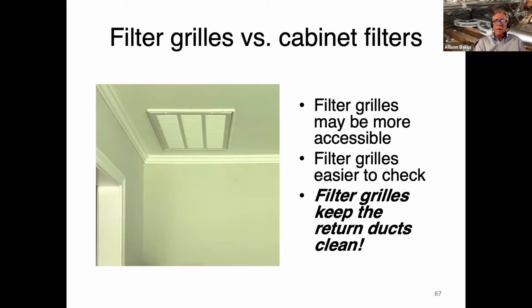One thing that you have to do, though, with filter grills is make sure the return duct is super tight, because any leaks in that return duct between the filter and the air handler are going to be sucking in air that doesn't get filtered. So the whole return duct has to be sealed absolutely tight, so you don't suck in dirt there, because that's under negative pressure.